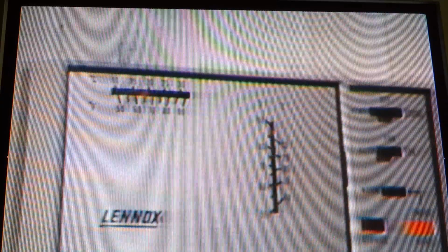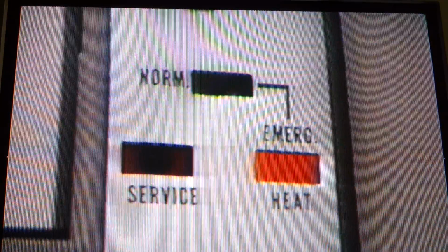Heat pump thermostats are specially built to handle an increased number of control circuits. Both electromechanical and digital styles are available. All have emergency heat mode override. Some thermostats are combined with an outdoor thermostat. This type control allows auxiliary heat only when the outdoor temperature drops below the balance point of the heat pump. With improved capacity and efficiency, the balance point of high-quality heat pumps is being lowered with each new design.